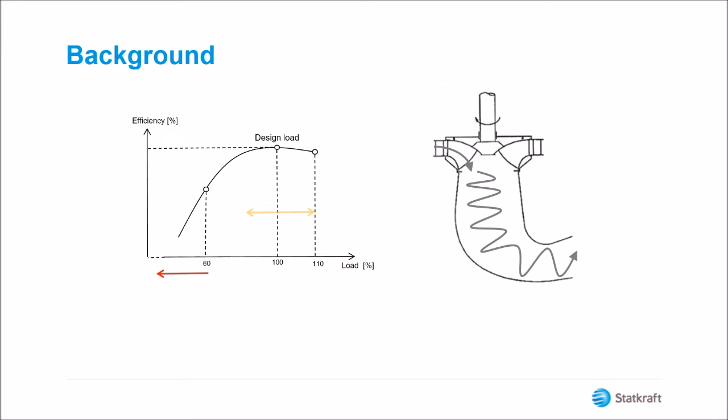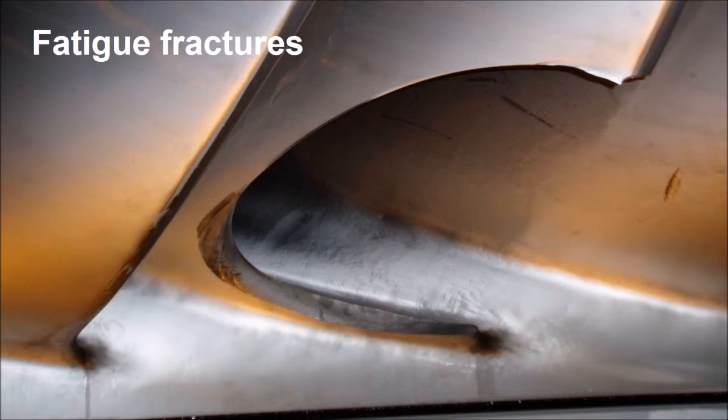At part load, where the efficiency has dropped heavily, and where the flow still is substantial, the rotation of the water will be such that heavy backflows and pressure pulsations can occur. These pressure pulsations can in time cause fatigue fractures to the runner.